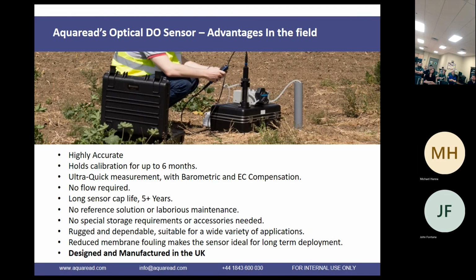So, advantages in the field: it is highly accurate, and the specification is very good - I have it to hand on my stand if anyone wants it. It holds its calibration for up to 6 months, which is pretty good, saving you from having to calibrate regularly. Obviously for some parameters you need more regular calibration, but not for this one. It takes 11 milliseconds to take a reading, so it stabilizes very quickly, even in a flow cell. You don't need any flow over the sensor either.